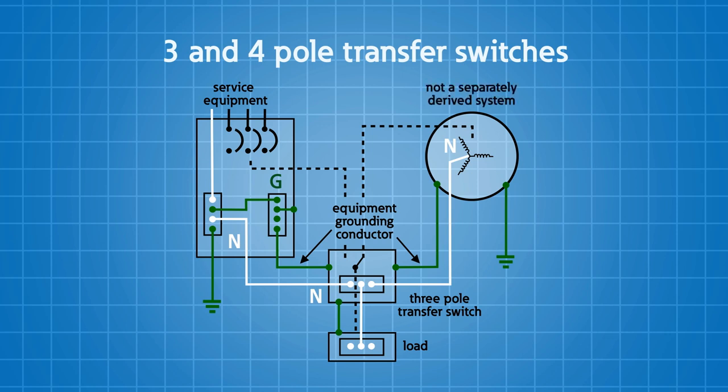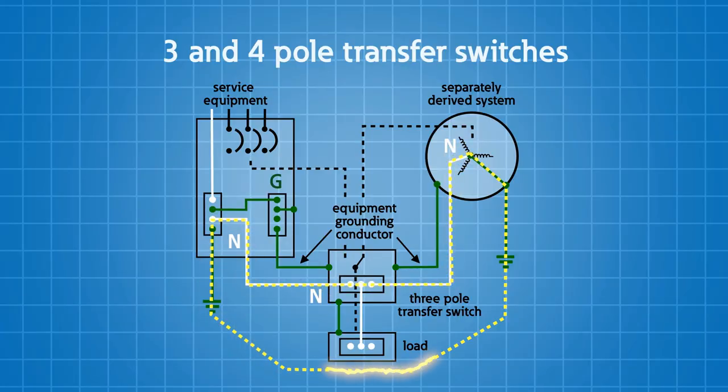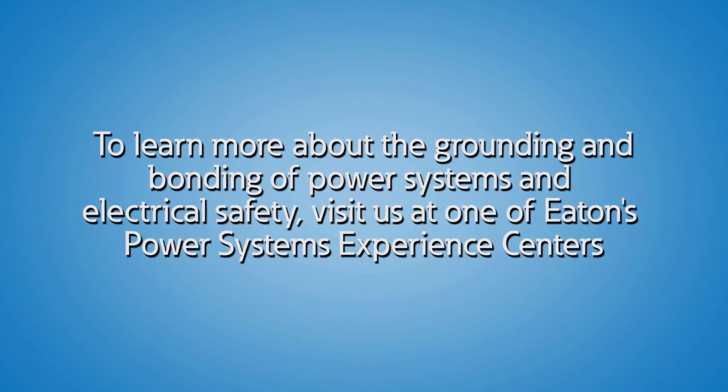But you must be extremely careful on how you operate a system like this, because the return current for the generator neutral will flow back through the other separately derived system or transformer. This is especially important for the electrical workers who will be servicing the equipment. Thanks.